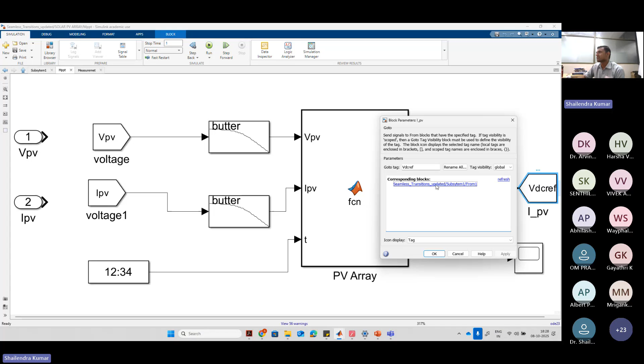So we have this inverter control, and in this inverter control we have taken this VDC. So VDC reference, in case of single stage, is not decided based on the grid voltage. It is derived from the PV array. Try to understand, right? So the PV array decides this VDC reference in this case of a single stage system.